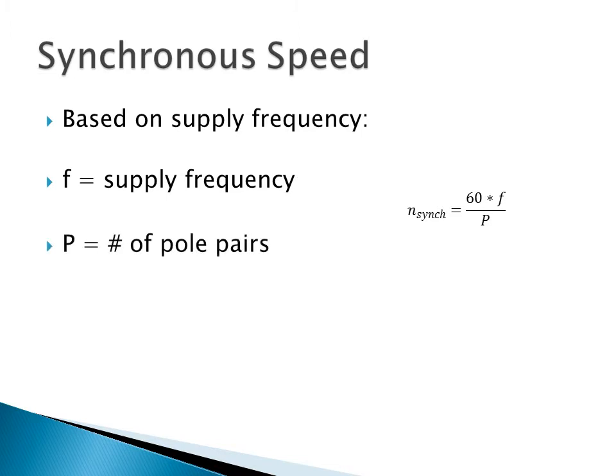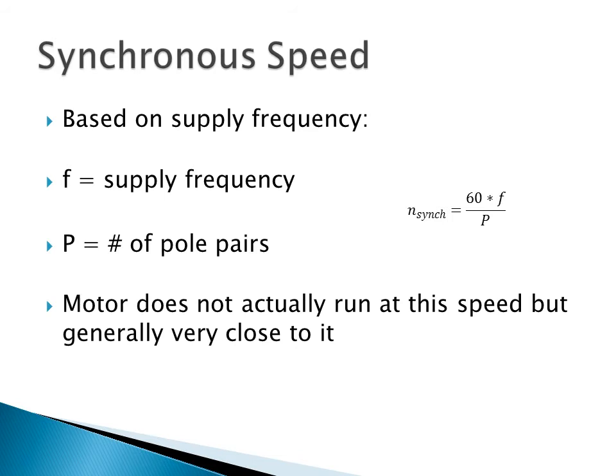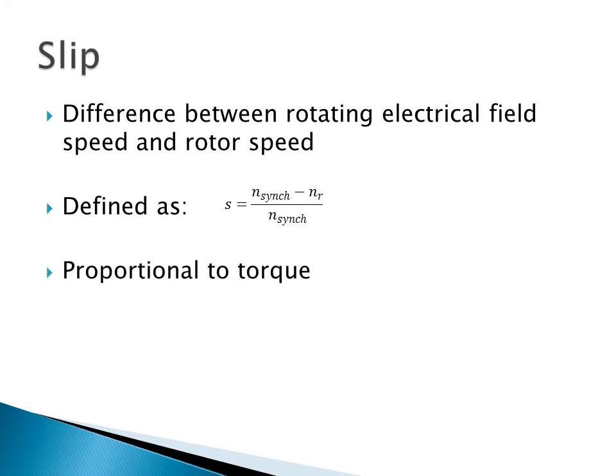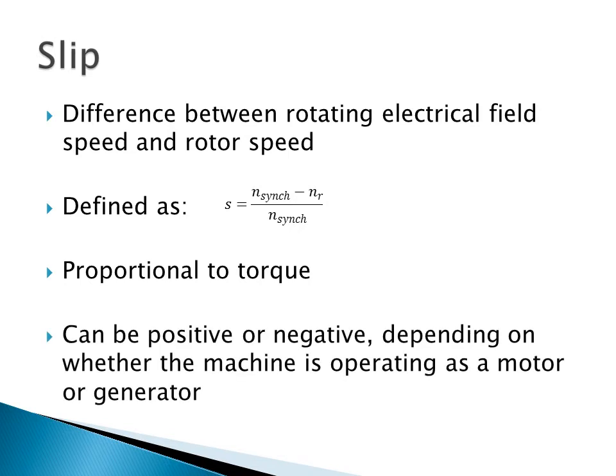Now, induction motors want to run at a synchronous speed, which is dictated by the supply frequency. They will, however, not actually run at this frequency. They'll run a little bit slower, depending on the load and how much torque there is applied to the motor. So, the difference between the rotating electric field speed and the speed of the rotor is called the slip. We can calculate it as the synchronous speed minus the rotor's actual speed divided by the synchronous speed. And it is generally proportional to torque when you're operating in the normal operating band of the motor.